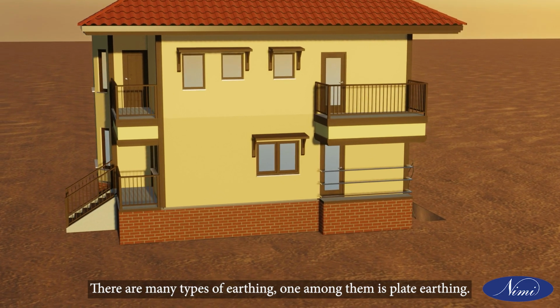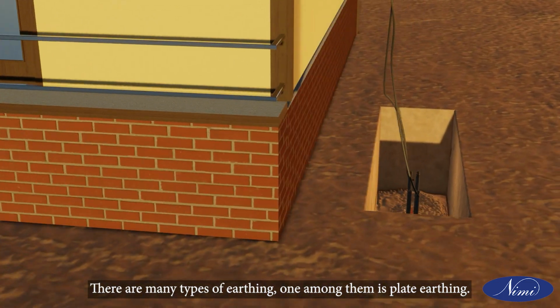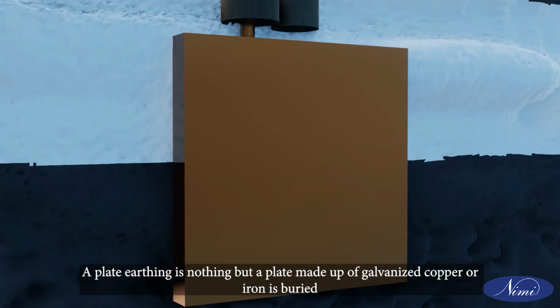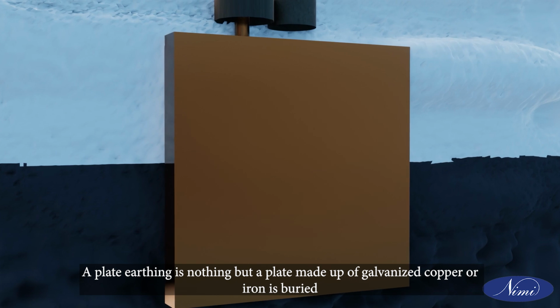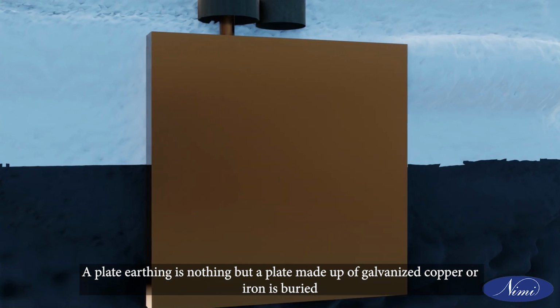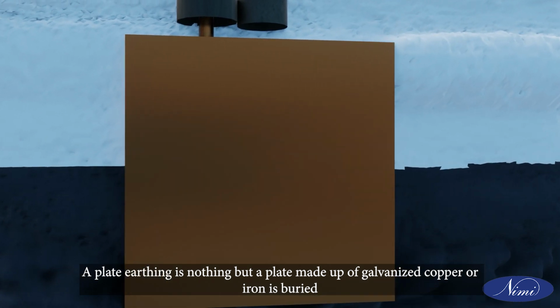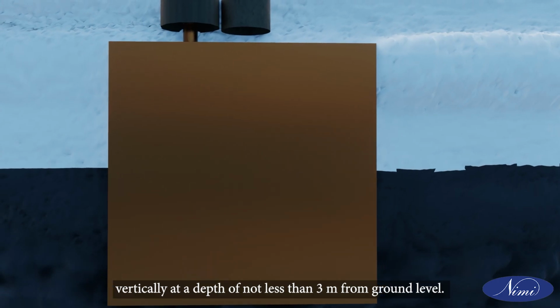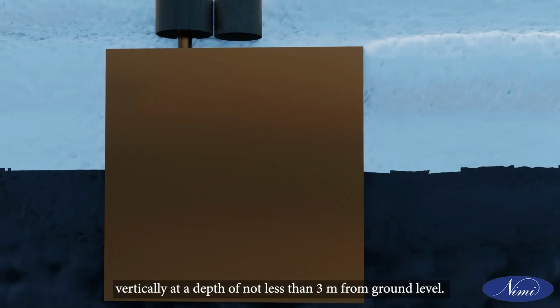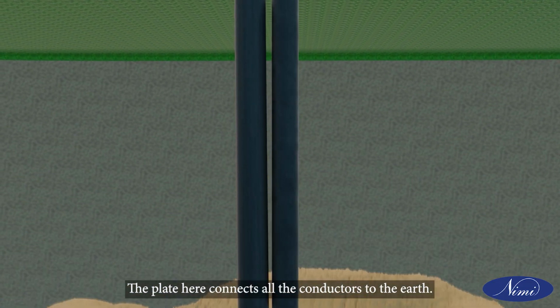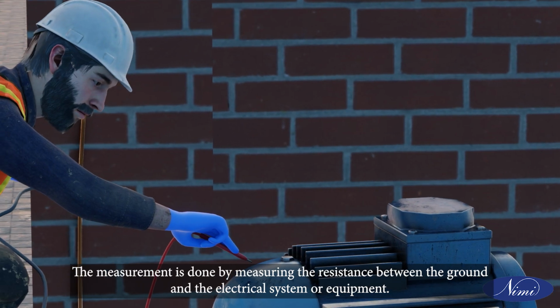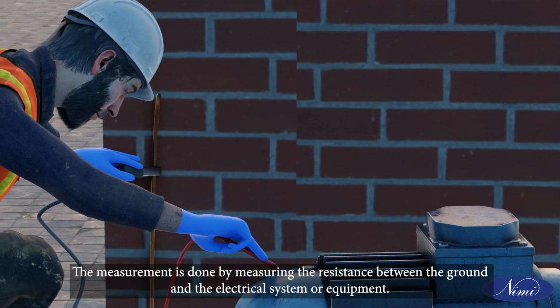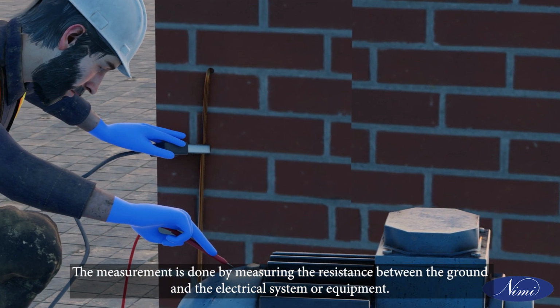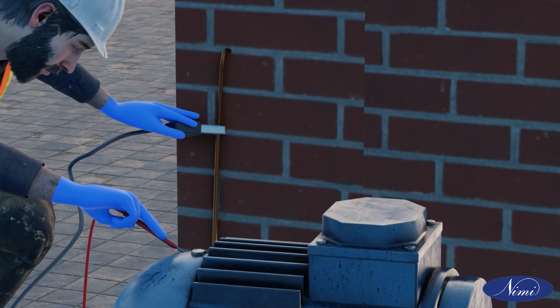There are many types of earthing. One among them is plate earthing. A plate earthing is nothing but a plate made up of galvanized iron or copper buried vertically at a depth of not less than 3 meters from ground level. The plate here connects all the conductors to the earth. The measurement is done by measuring the resistance between the ground and the electrical system or equipment.